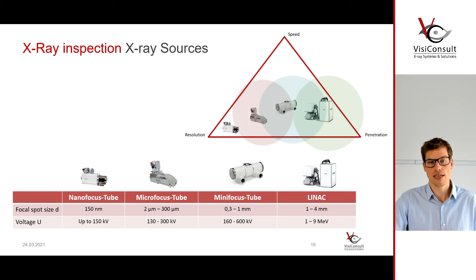One last hint, it's again a bit technical, is that X-ray is a cone beam technology, which means to achieve more resolution, right, you have to magnify. That means you have to move the part closer to your X-ray tube. If you do this, at the same time your field of view is reduced. Typical detectors that are used for computer tomography are 40 by 40 centimeters, right? And if you have a magnification of close to 1, so you're very close to the detector, you can scan a part of 40 by 40 centimeters. But you are limited to the resolution of the detector, let's say 100 micron.